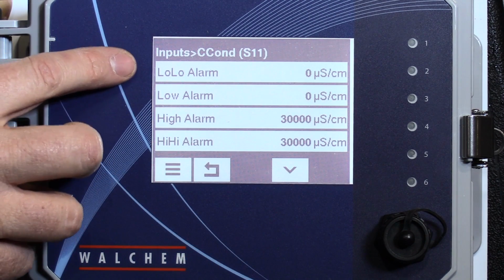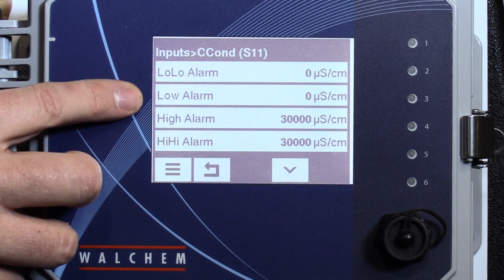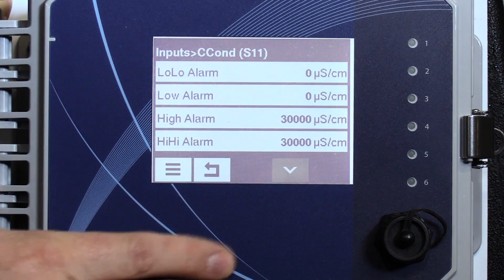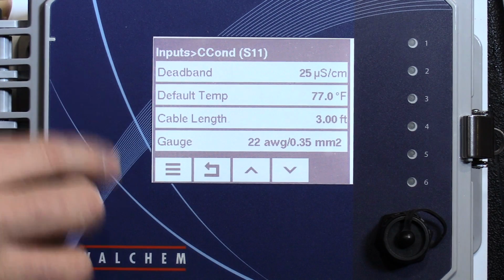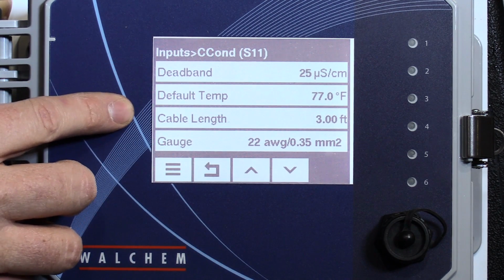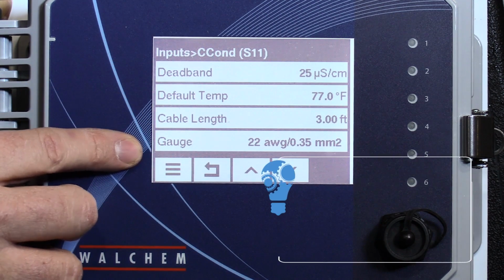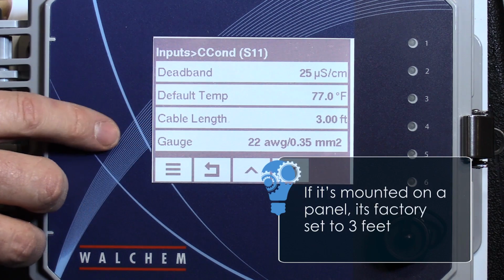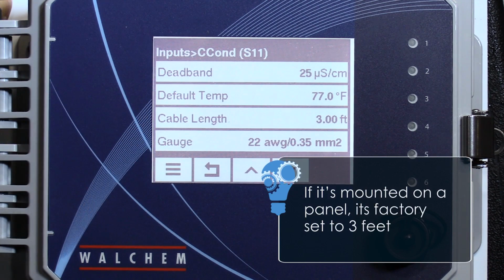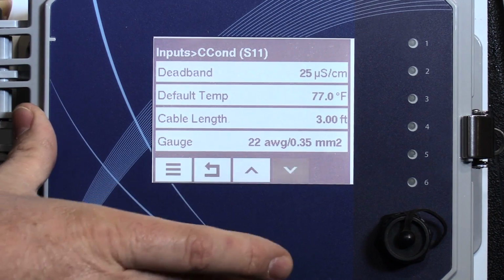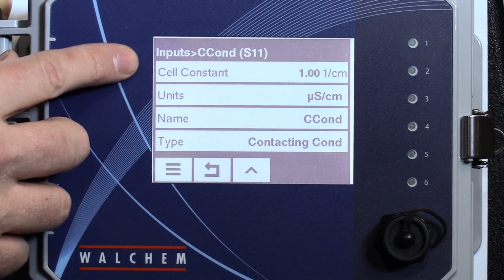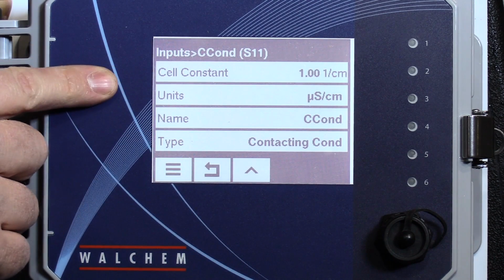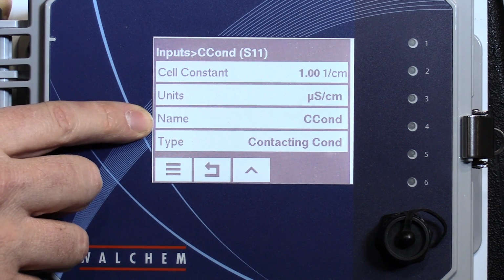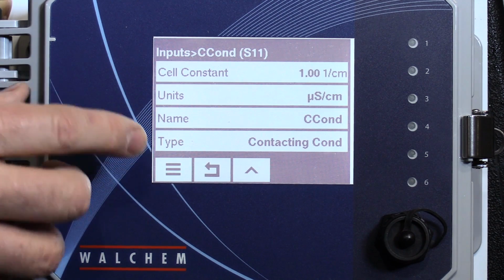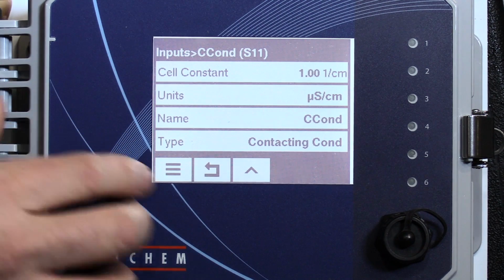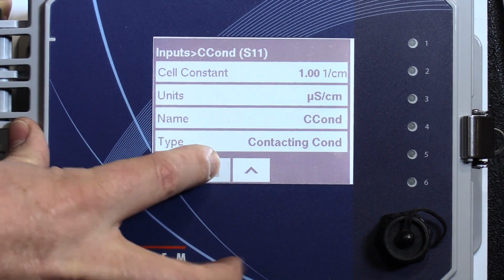You would set your alarms, your low alarm, high and high high alarm, your deadband, the default temperature, how long the cable is, and the gauge. If it's mounted on a panel, it's factory set to 3 feet. You do not have to change that. The cell constant will be there, the units will be there, and you can change the name to read conductivity, tower water, whatever you would like it to be. Once you've done that, you go back.